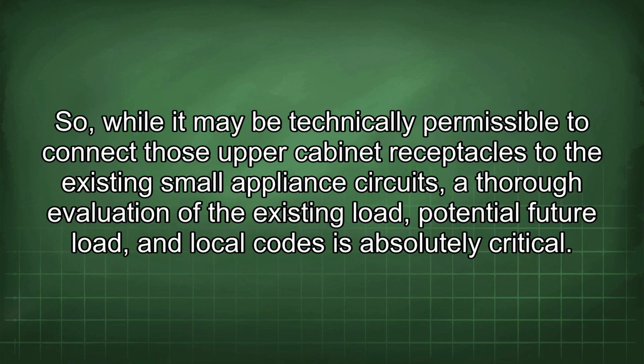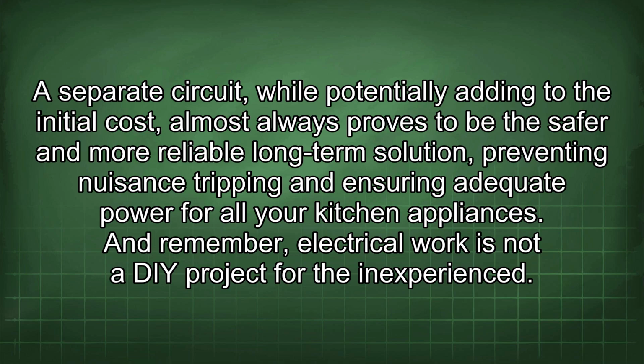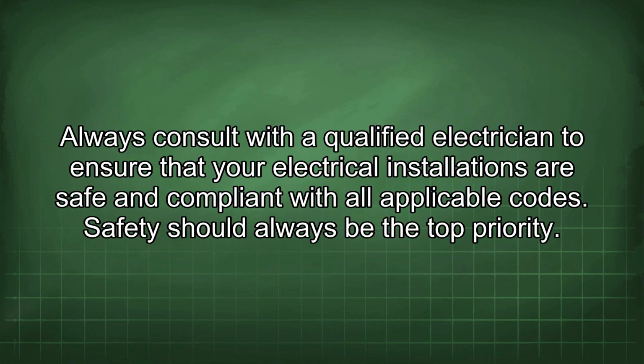So, while it may be technically permissible to connect those upper cabinet receptacles to the existing small appliance circuits, a thorough evaluation of the existing load, potential future load, and local codes is absolutely critical. A separate circuit, while potentially adding to the initial cost, almost always proves to be the safer and more reliable long-term solution, preventing nuisance tripping and ensuring adequate power for all your kitchen appliances. And remember, electrical work is not a DIY project for the inexperienced. Always consult with a qualified electrician to ensure that your electrical installations are safe and compliant with all applicable codes. Safety should always be the top priority.